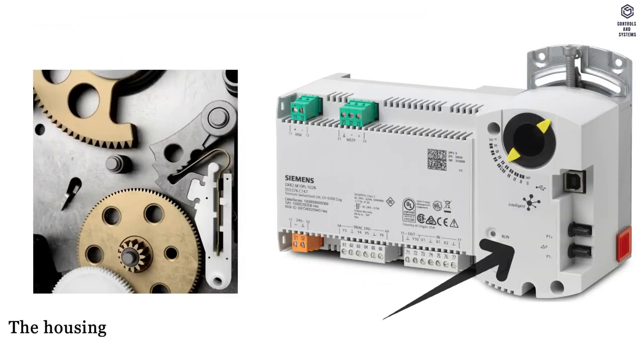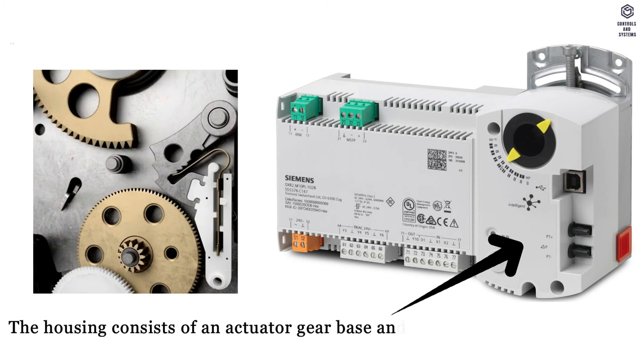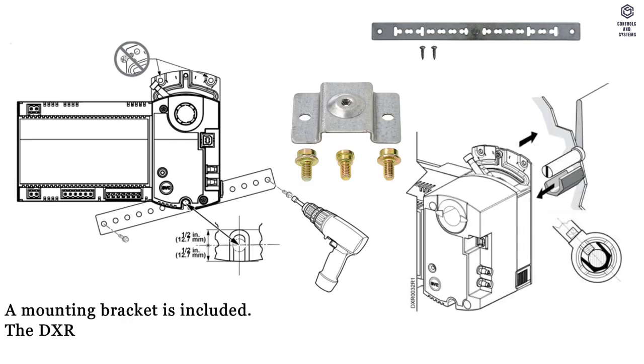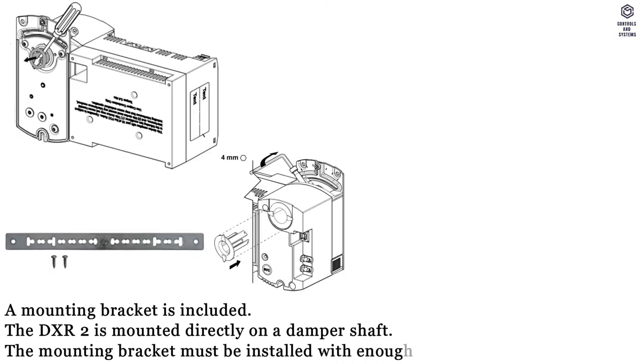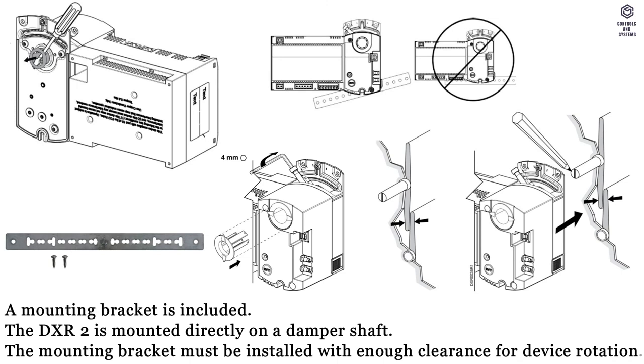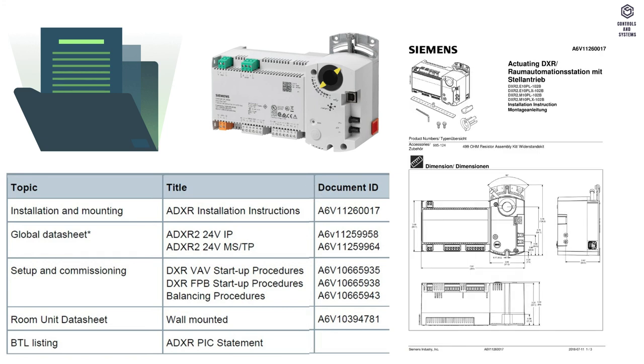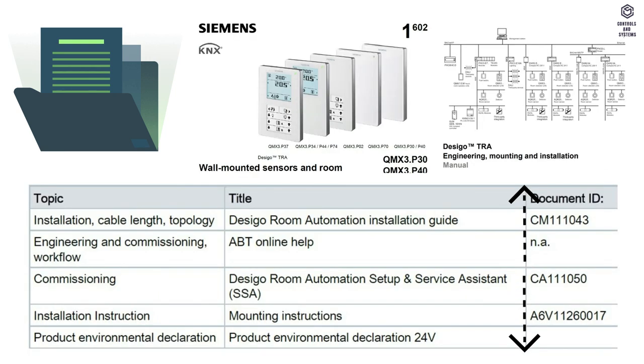Mounting: the housing consists of an actuator gear base and the device housing, which accommodates the main circuit board. A mounting bracket is included. The DXR2 is mounted directly on a damper shaft; the mounting bracket must be installed with enough clearance for device rotation. Documentation: the product documentation table indicates the related topic, title, and document ID for this DXR2.M10 series automation station device.